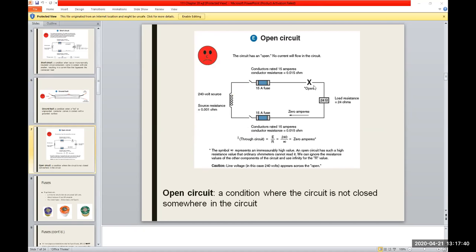And then you get something where you have an open circuit, where it's just a complete break in the line, and nothing happens. Current has to have a path to follow, and if you get an open circuit, you will get zero current in the return. There's just nothing happening. And of course, you won't trip your fuse or your circuit breaker. I'll tell you what, this problem is more common than you think. You get this open circuit caused by different things, but that'll be one of the biggest troubleshooting problems you ever run into.